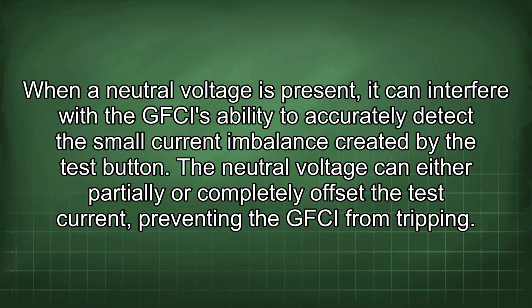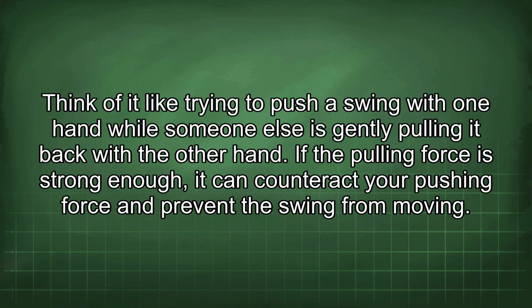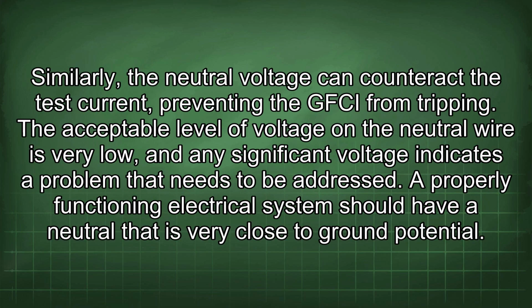When a neutral voltage is present, it can interfere with the GFCI's ability to accurately detect the small current imbalance created by the test button. The neutral voltage can either partially or completely offset the test current, preventing the GFCI from tripping. Think of it like trying to push a swing with one hand while someone else is gently pulling it back with the other hand. If the pulling force is strong enough, it can counteract your pushing force and prevent the swing from moving. Similarly, the neutral voltage can counteract the test current, preventing the GFCI from tripping.